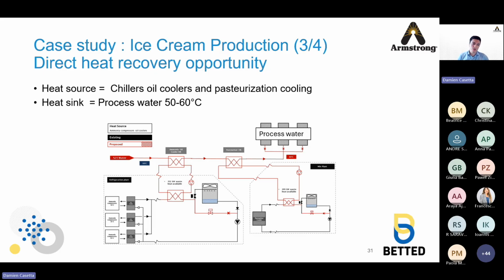So what can be done to improve efficiency of this typical ice cream production? First thing to do is to make use of direct heat recovery. Remember, Pinch is telling us how to maximize this. Here is an example. Source is the oil coolers from the chillers and pasteurization cooling. These two we've just seen in the previous slides. And the sink is the processed water at 50 to 60 degrees.